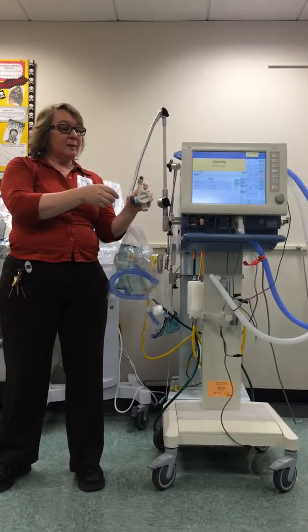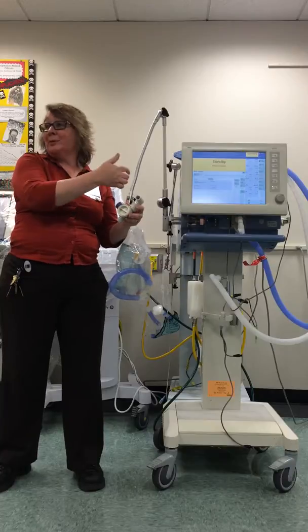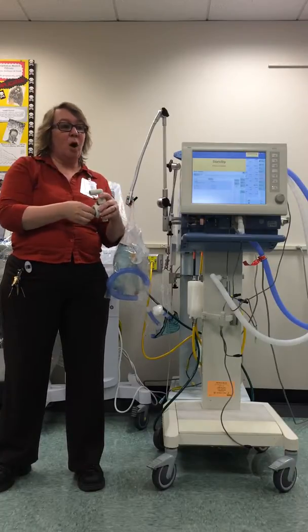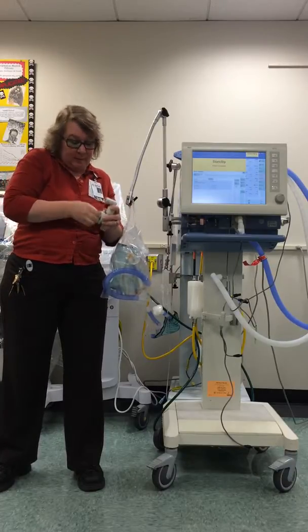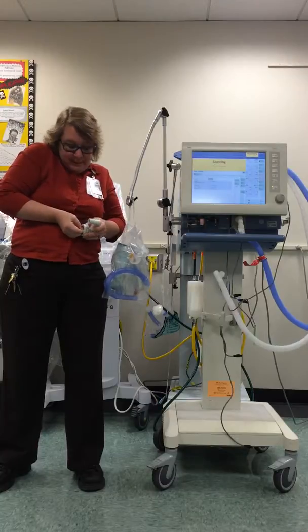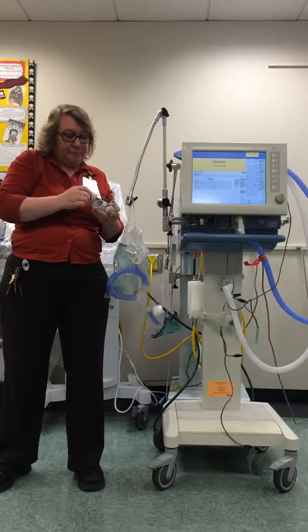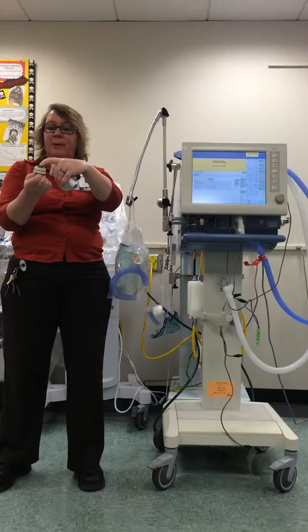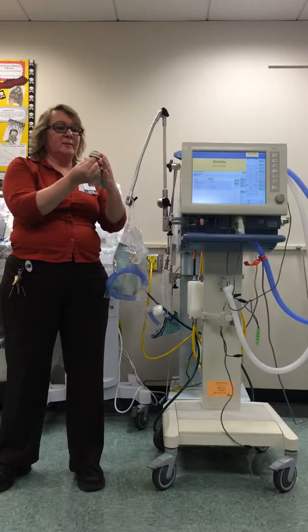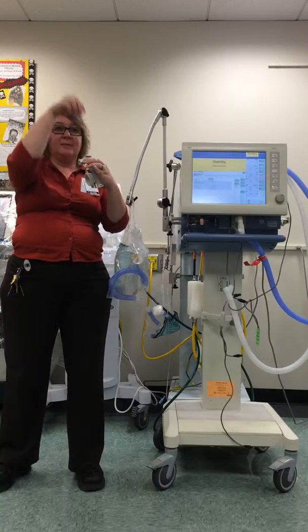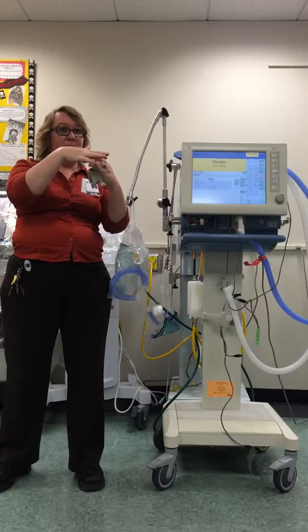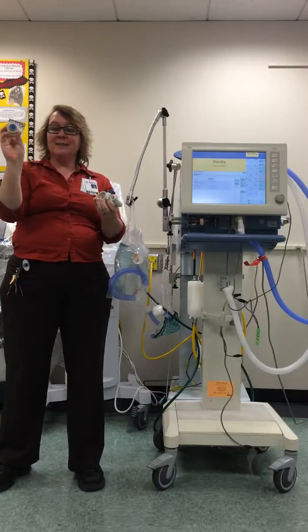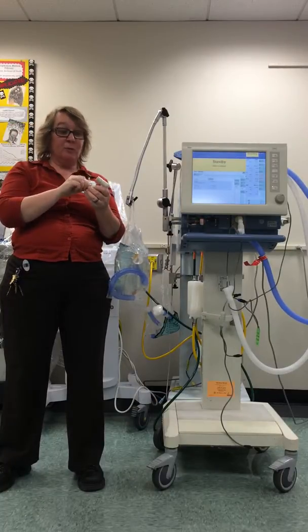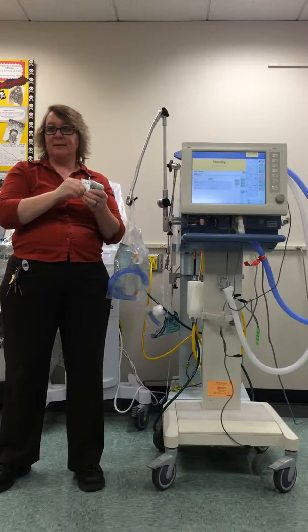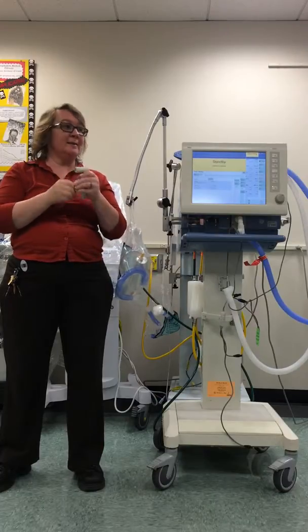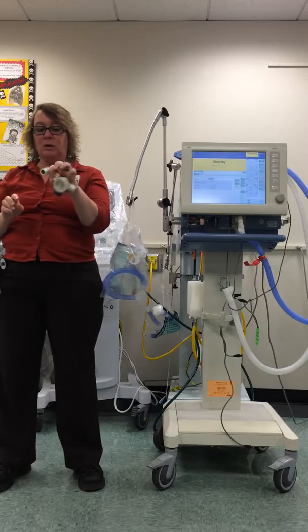So this one is the external exhalation valve. Some of them are built inside, and I'm going to show you all of them next week and tell you more about it. But this has to be tight, and it's hard to unscrew. They all have little diaphragms with magnets on it. So when it's ready to close off, the magnet just lifts up, and when it's ready to open, it goes down. So things can get stuck inside of these, like mucomyst, so that's why we put filters on the exhalation side, because we don't want water or anything in this, because if we do, it doesn't work.